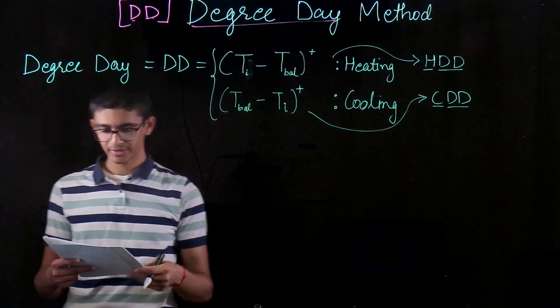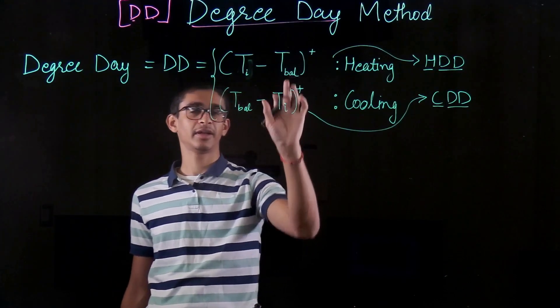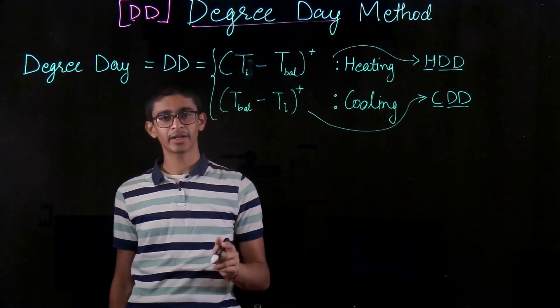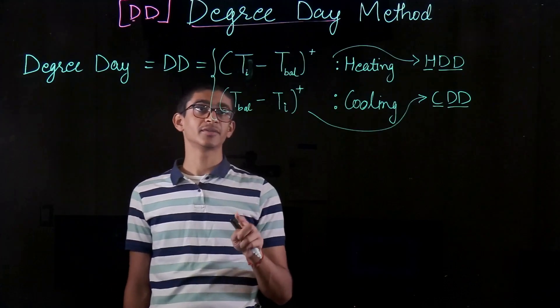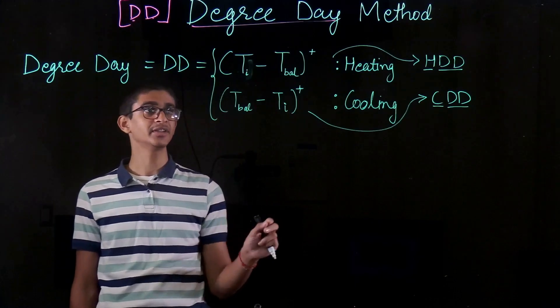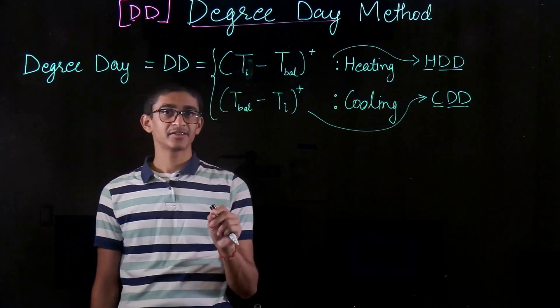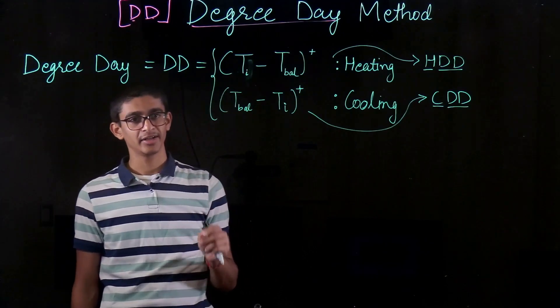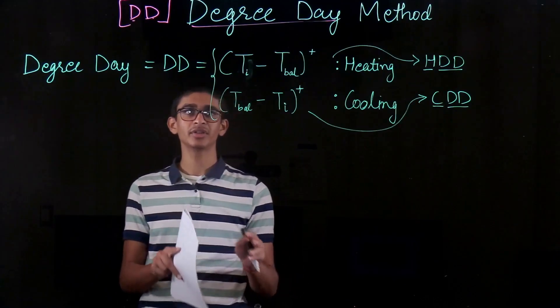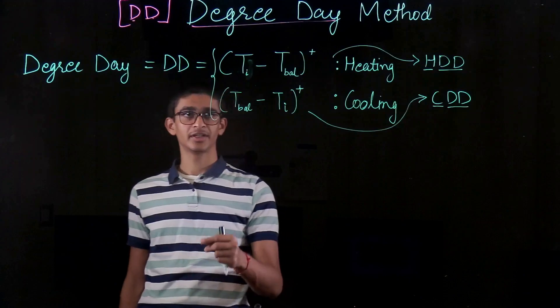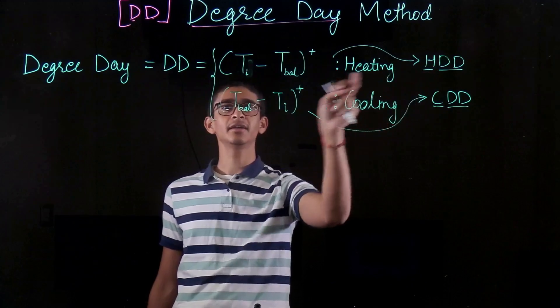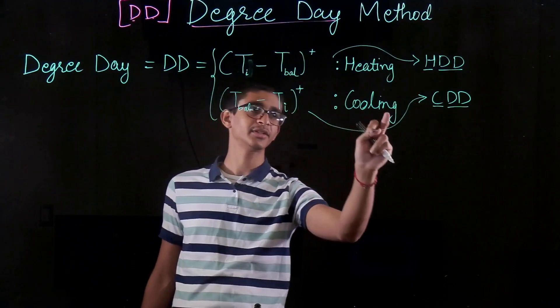T_balance is an outside temperature — not an indoor temperature. It is the outside temperature at which the building does not require heating or cooling. That means the outside temperature is such that the heat gain in the building exactly equals the heat loss from the building, so there is no requirement for heating or cooling. If indoor temperature is greater than T_balance, I need heating; if T_balance is greater than indoor temperature, I need cooling.